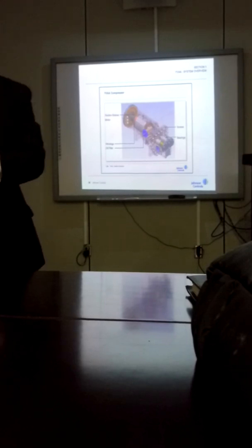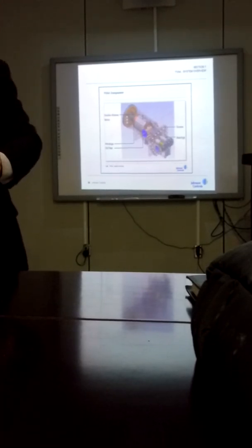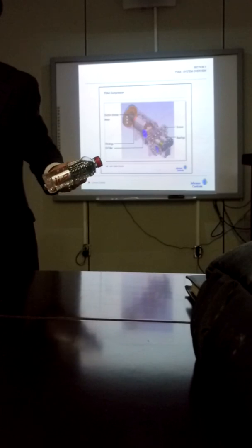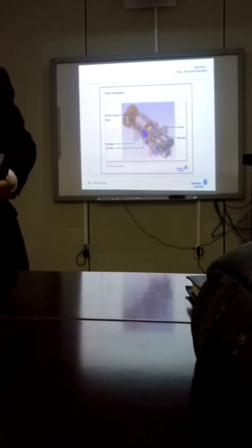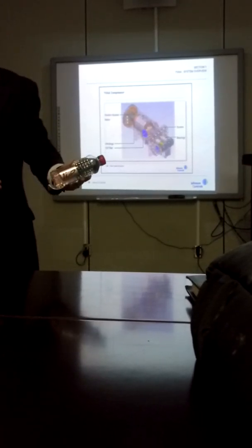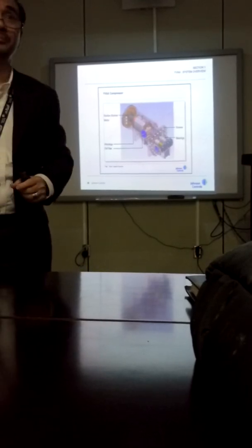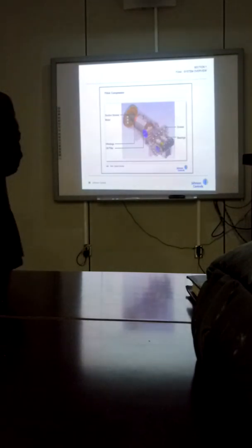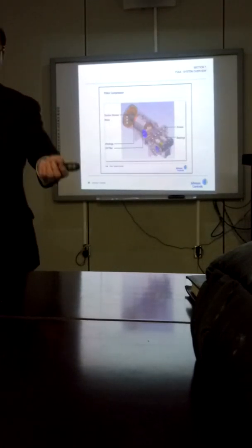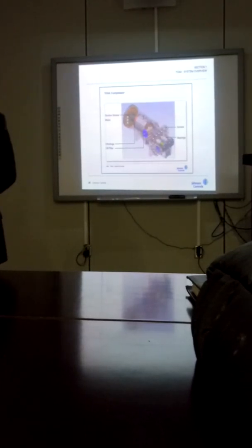Unless the water becomes like coffee, then you need to change the oil. The number of hours of the machine doesn't require you to change the oil. Unlike other conventional chillers, where there's a 5,000 hours oil change, it shows in the operation and maintenance.